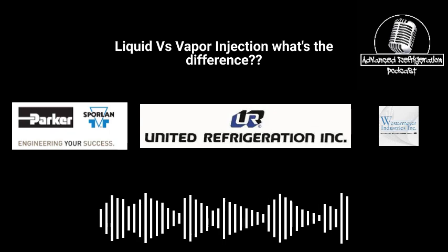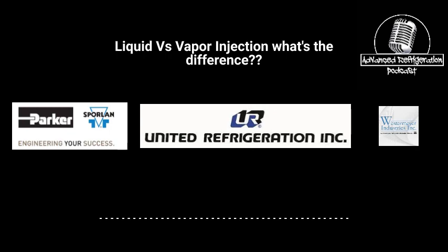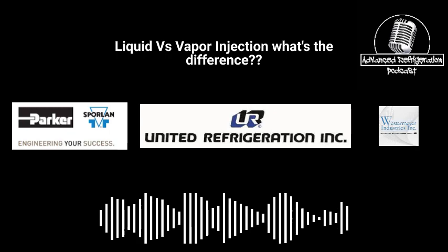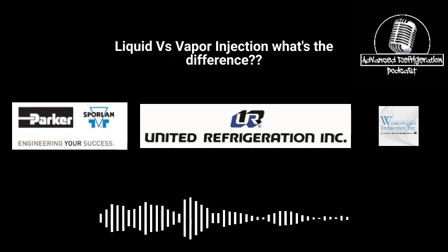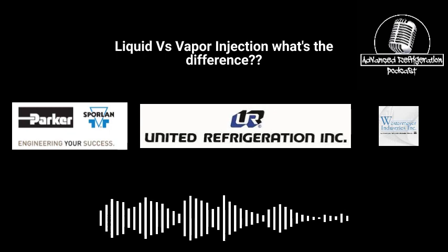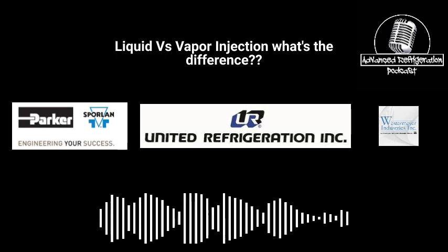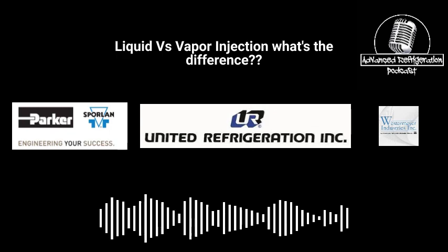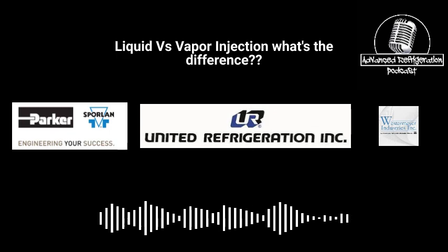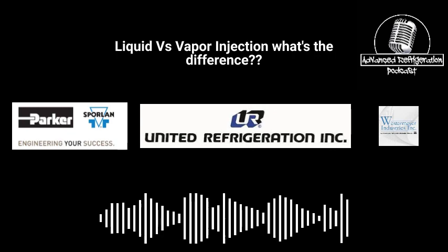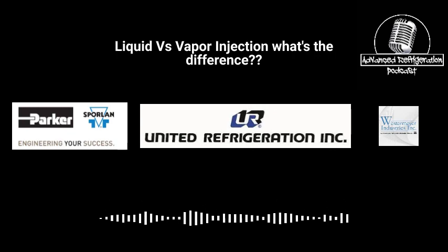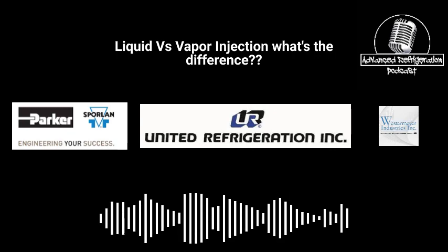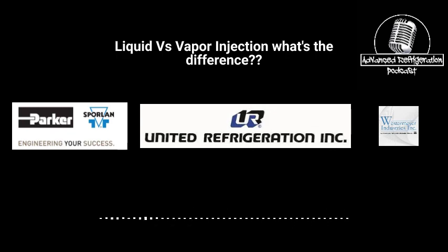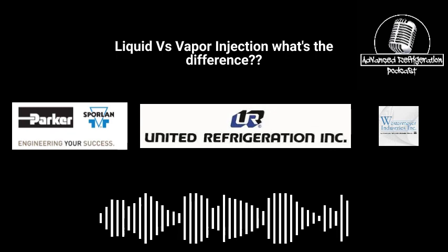Also, make sure those are wrapped on the bulbs or any sensor or anything that's controlling any type of liquid injection. Make sure it's wrapped, because you'll be like me and look like an idiot because you didn't read the directions. So I didn't, 'cause I'm being a manly man. And so then I find out that it wasn't working because of that. And also, when it's tied to the pipe, use stainless zip ties or TXV bulb straps. 100%, the TXV bulb straps are better because you get more surface area on there with the copper. So you want to use that.